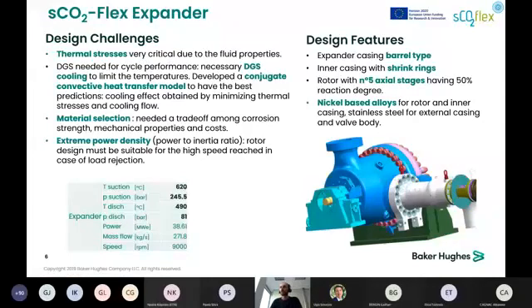For this reason, and considering a possible full load rejection that can happen during the entire turbine lifetime, the design choice was to use nickel-based alloys for the rotor and inner casing instead of standard martensitic steel, which has been kept for the external casing and valve body. Also for the expander, the sealing system is a key point. In fact, the dry gas seal system is the most effective technology to minimize leakages. But it is well known that the operating temperature should not exceed 250 degrees. For this reason, a dedicated cooling system has been designed in order to cool down the hot gas in contact with the seal system.